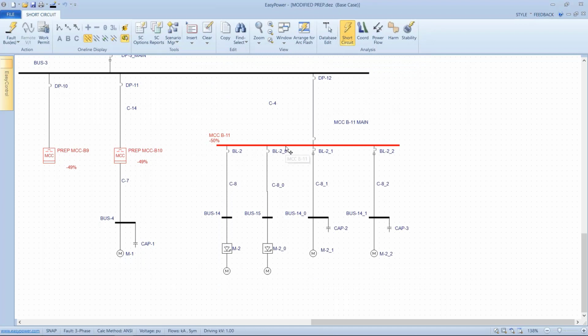If I start to add current or loads, again, what we're talking about is the maximum current on this bus during a half cycle fault. And by setting the control system like this, when I start to go through what ifs, I can tell if I'm coming close to the ratings for at least these buses. But that's just one way to deal with that particular aspect of it. All right, back to coordination.